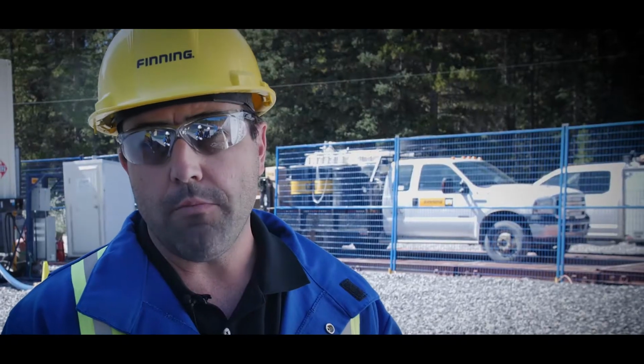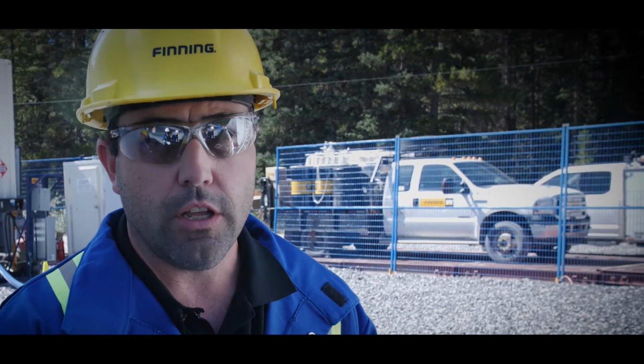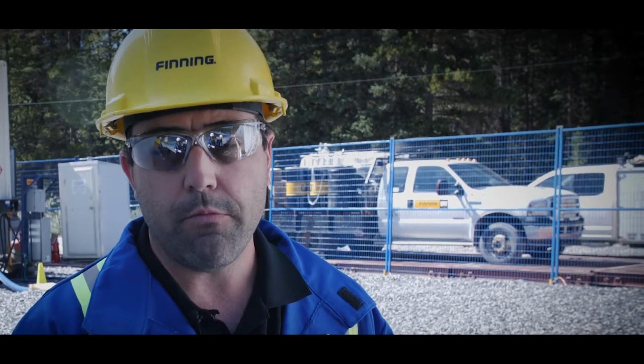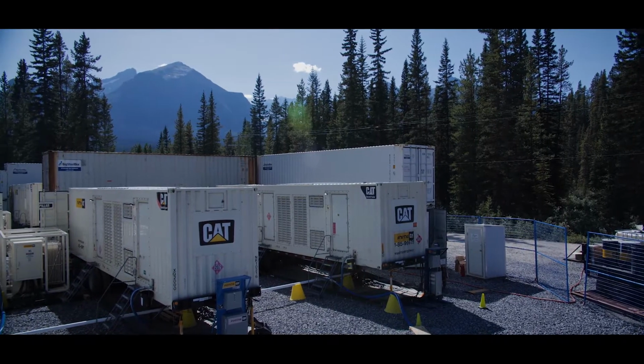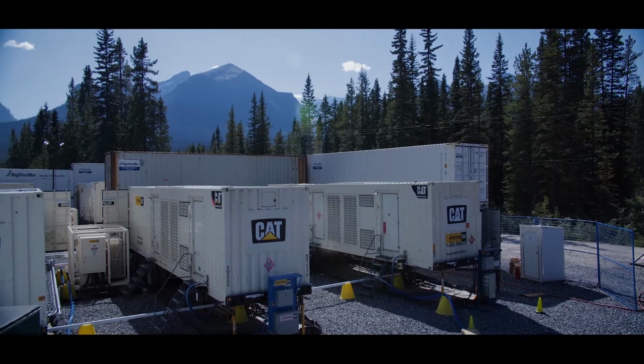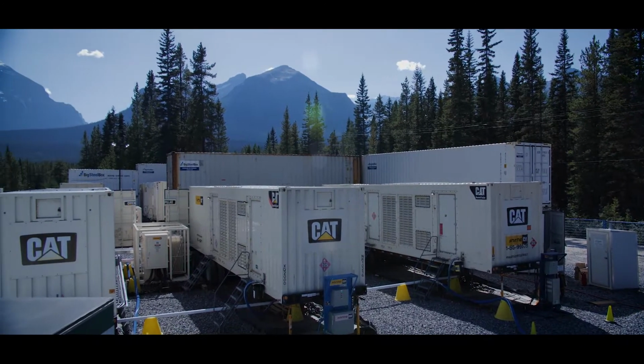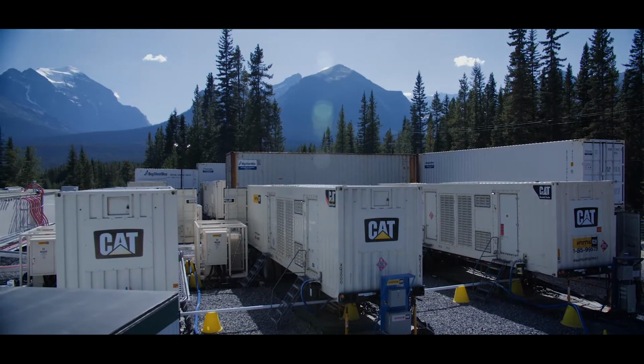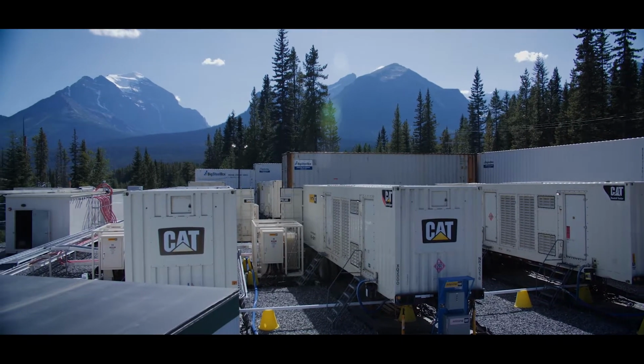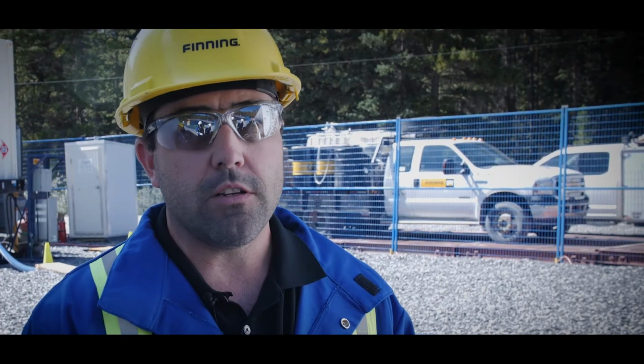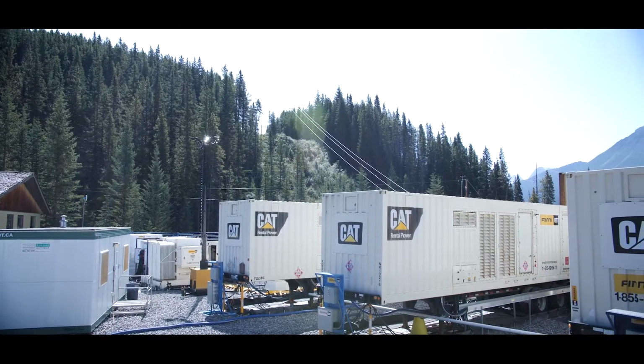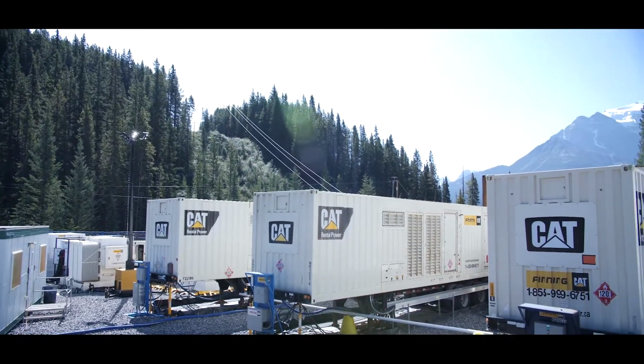It really comes down to reliability and how we can continue to provide AltaLink with 100% reliability and uptime of power. One of the things we've incorporated into the project is redundancy. What that allows us is if we happen to lose one generator on our system, the other 3 units online will still be able to pick up the entire load, and then we have a PLC that will sense that and bring on the next available generator.